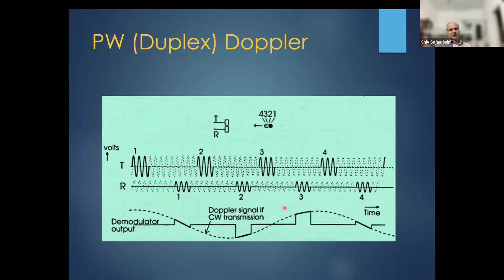It depends upon how much Doppler shift happened during that very narrow period. So once it overlaps, it calculates that okay, this was the Doppler shift, and this is the actual Doppler shift which is received. And this is the perceived Doppler shift, where the dotted line is joining the actual ones, the bold ones. So this is what the machine calculates, and this is almost invariably faulty, especially if the signal is having a very high speed.